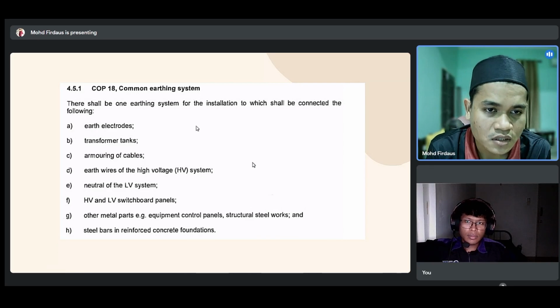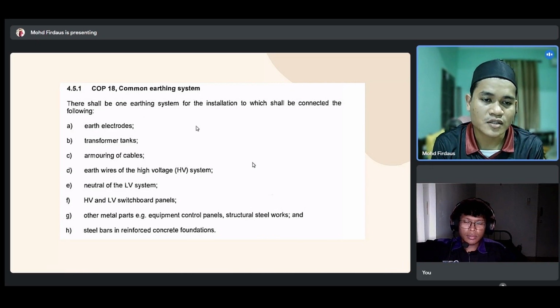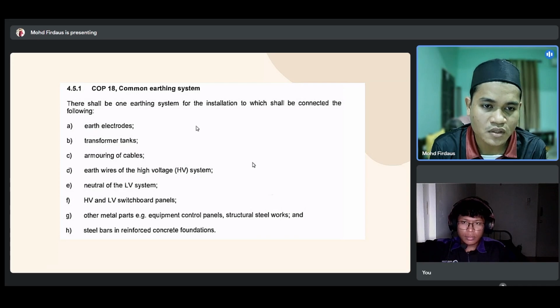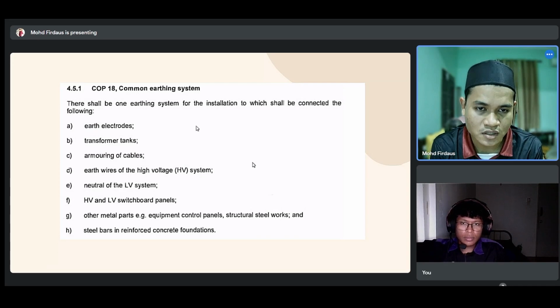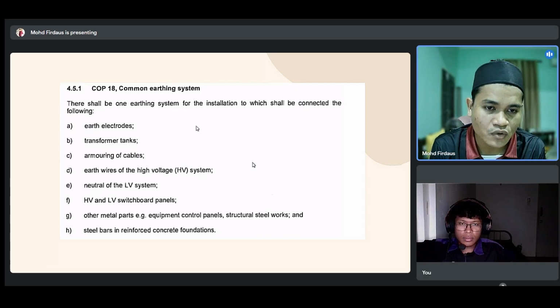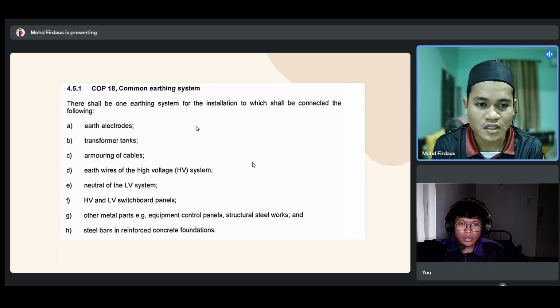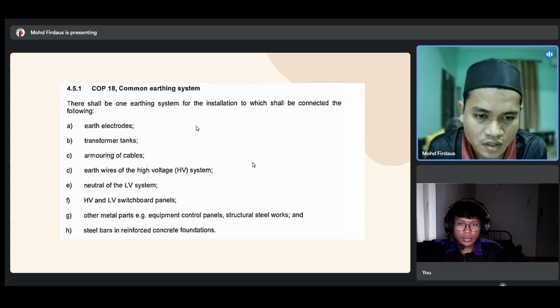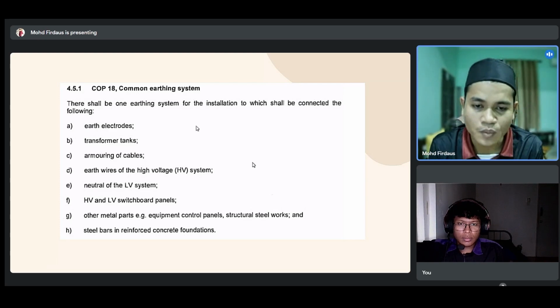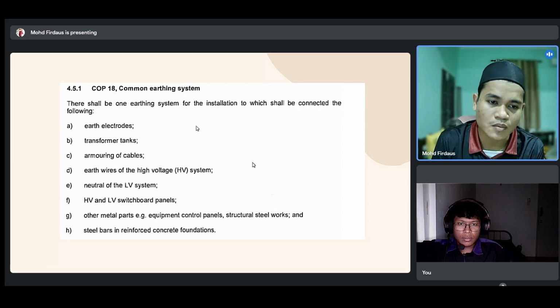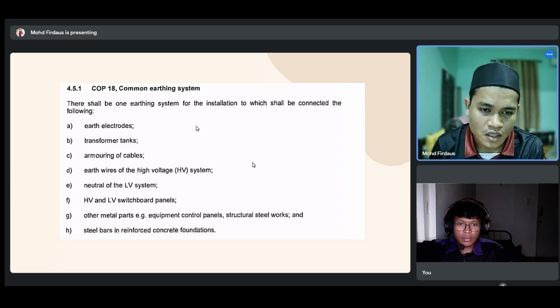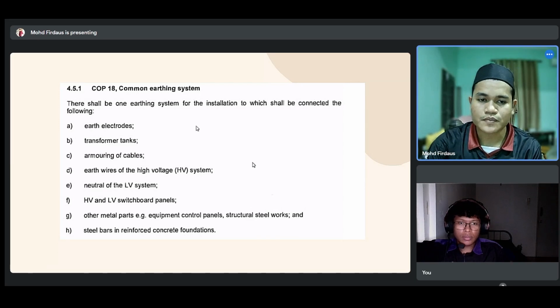First: earth electrode, transformer tanks, armoring of cables, earth wire of the high voltage system, neutral of the low voltage system, high voltage and low voltage switchboard panels, other metal parts such as equipment control panels, structural steel work, and steel bars in reinforced concrete foundations.